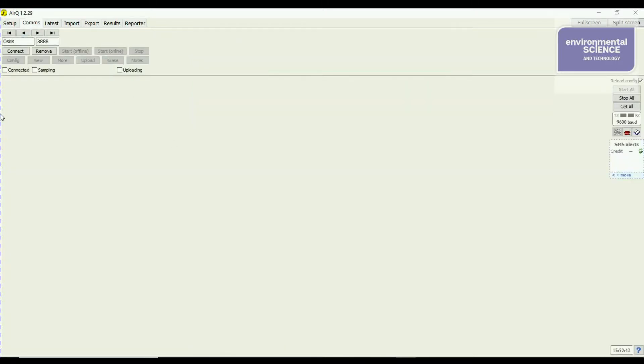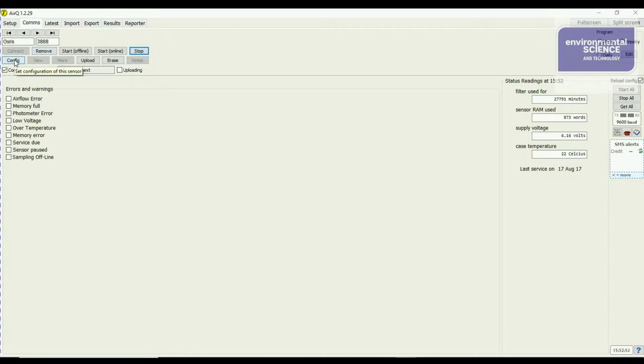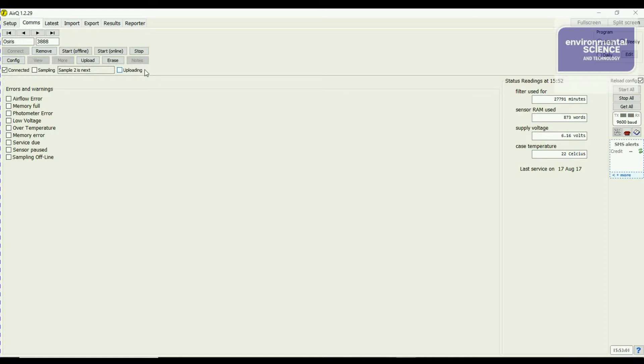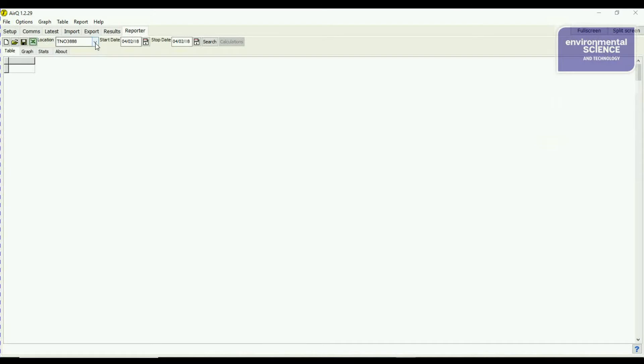Click over to Comms. First, stop the dust monitor from sampling — click stop, otherwise you can't proceed. You can then enter the configuration or click upload to retrieve the results. Click upload and the results are downloaded.